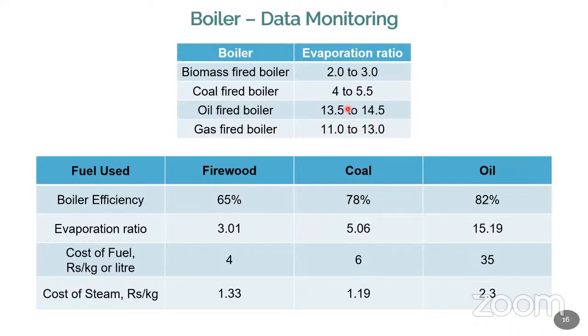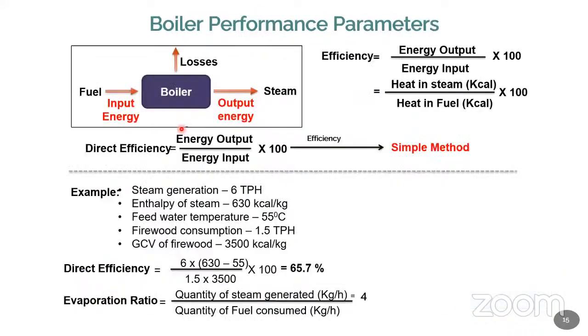So with the help of this chart, you can find out whether your boiler is properly working or not. Now let me come to the point of this elaborately, how to calculate this evaporation ratio. I can easily calculate the quantity of fuel input. How many kg per hour for 1 hour? How much fuel do I put in the chamber? I can measure it with the help of a digital weighbridge. This is very simple.